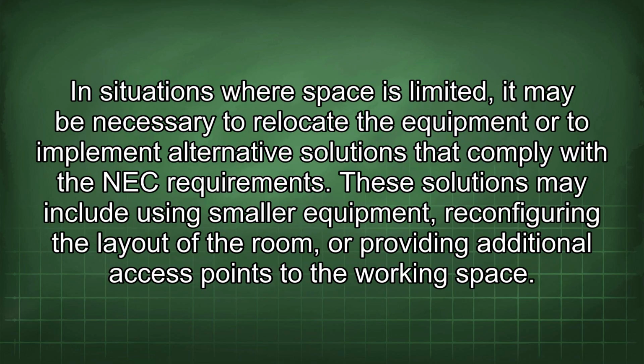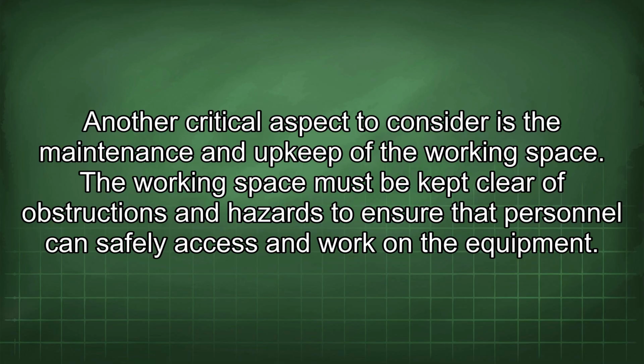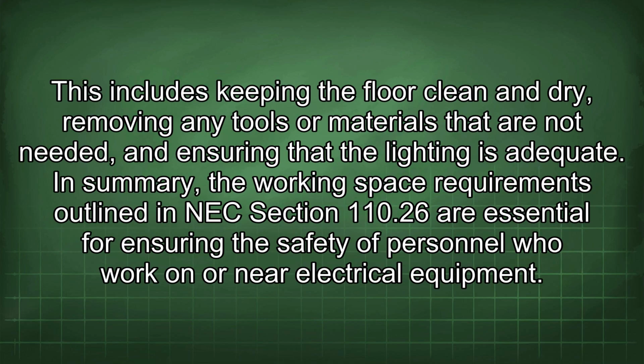In situations where space is limited, it may be necessary to relocate the equipment or to implement alternative solutions that comply with the NEC requirements. These solutions may include using smaller equipment, reconfiguring the layout of the room, or providing additional access points to the working space. Another critical aspect to consider is the maintenance and upkeep of the working space. The working space must be kept clear of obstructions and hazards to ensure that personnel can safely access and work on the equipment. This includes keeping the floor clean and dry, removing any tools or materials that are not needed, and ensuring that the lighting is adequate.